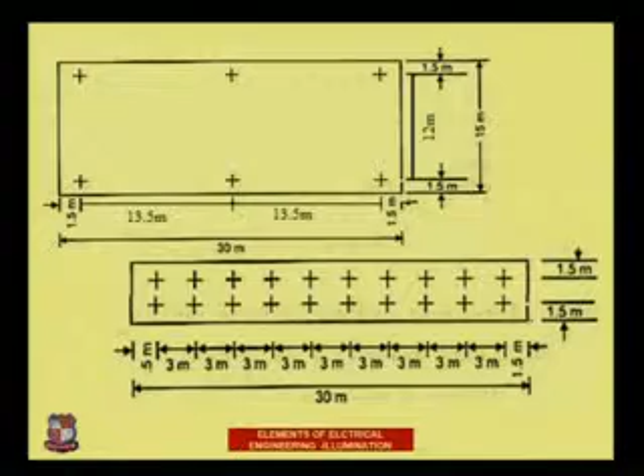Are you getting this? See, if the figure is given in such a way that there are a total of 3 light fittings, the distance between 1 and 2 is kept constant, and between 2 and 3 is also kept constant, but the distance is so far that the middle portion, or in-between portion, would not be properly illuminated, so there would not be an equal amount of illumination. In the second figure, the distance between light fittings is kept constant, but they are so near that there would be high intensity of light and it would create glare. So this condition should not arise when we are designing any lighting scheme for a particular premises.